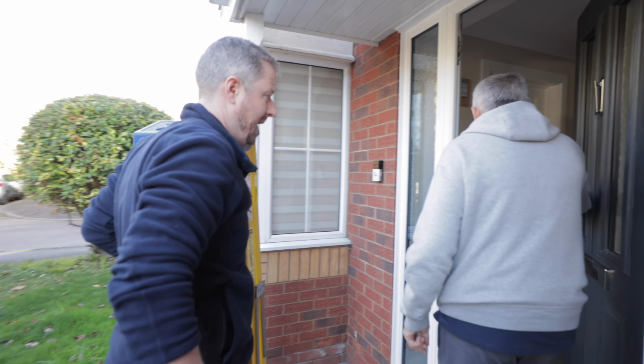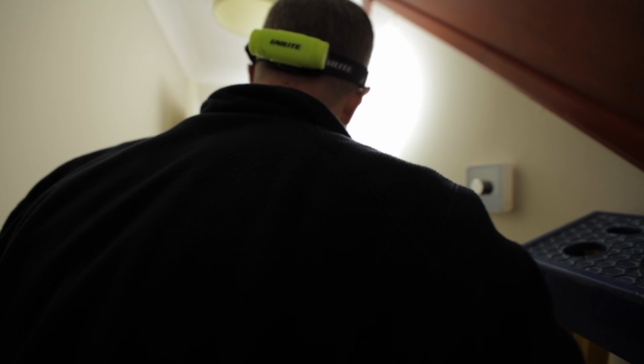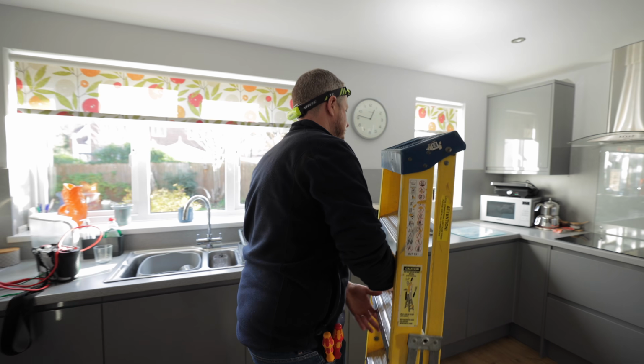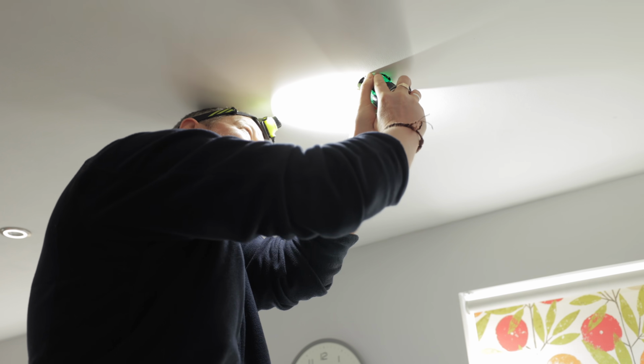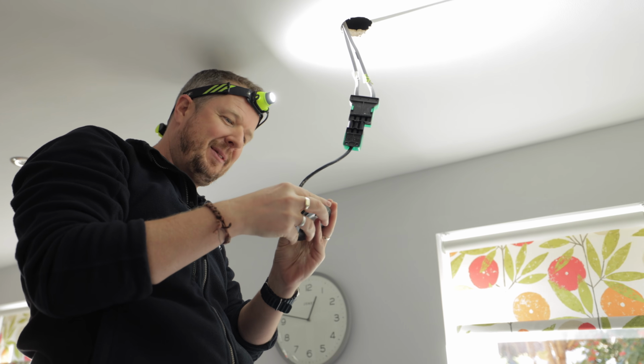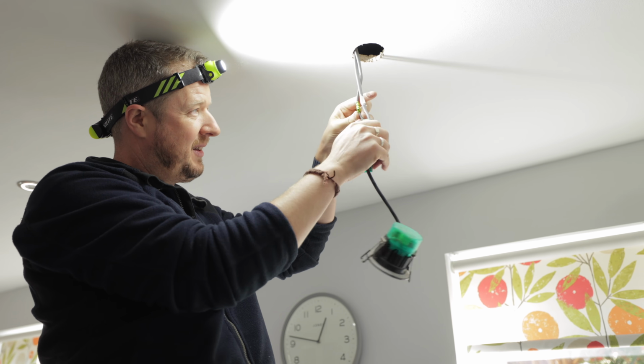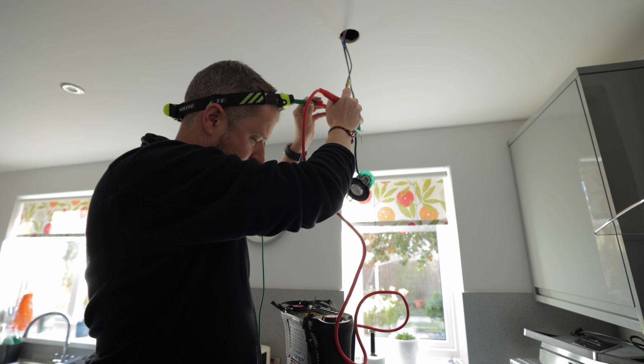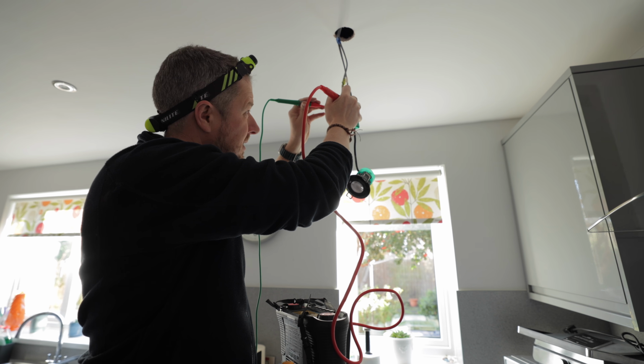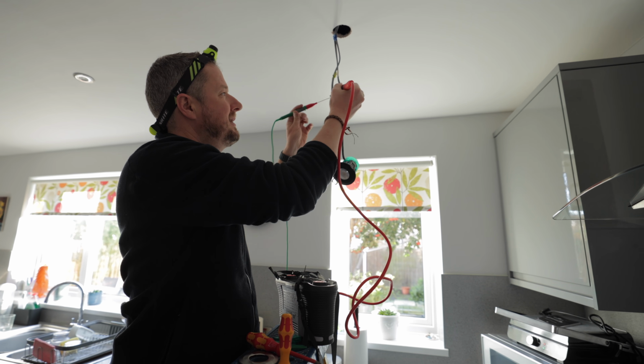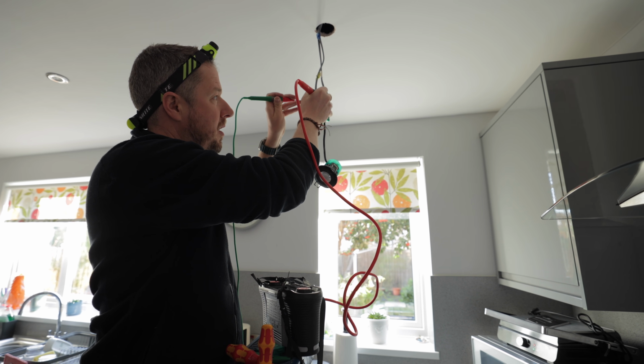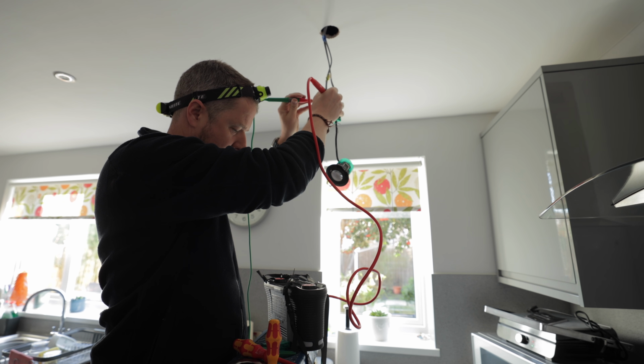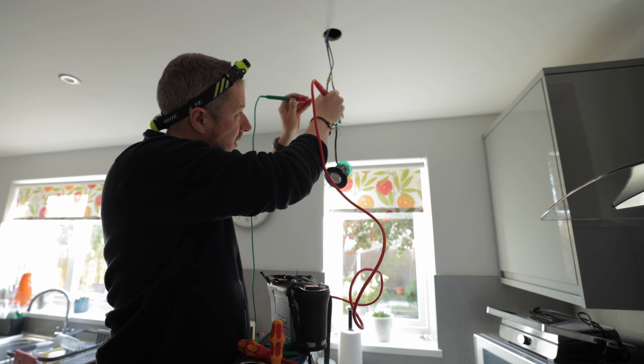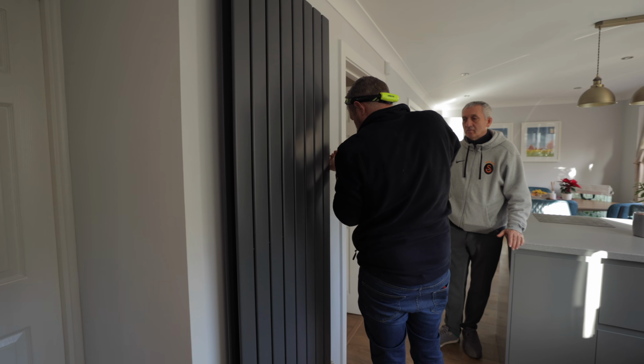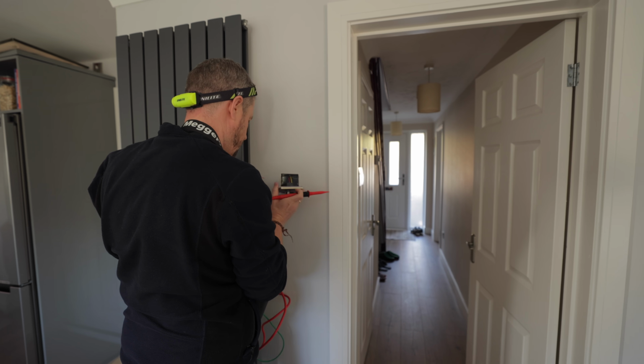Have you had any lights fitted up recently or anything like that? In the kitchen. In the kitchen? Yeah. Okay, well, I'm going to take one down if that's okay, just have a little look. Okay, it doesn't look too bad to be fair, it actually looks like it's been done properly. Okay, that's a very high resistance there. It's bizarre because when you're testing a dimmer, sometimes the resistance can be quite high because that's how a dimmer works, it basically puts resistance onto the circuit. I think I'm going to have to take the dimmer off, bridge it out, and then see what we get.